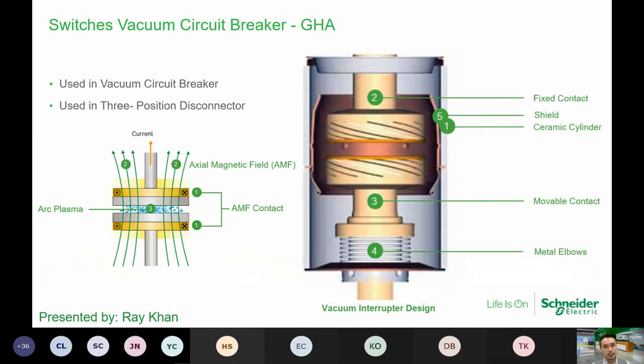Inside the GHA, we actually use the circuit breaker, which a lot of the time we hear of as the vacuum circuit breaker. The vacuum circuit breaker is also gas filled, and in a way it is not accessible for maintenance. The gas circuit breakers use SF6 gas for insulation, but a certain design is required to interrupt the arc. The arc interruption is actually done using the design of the vacuum interrupting chamber.